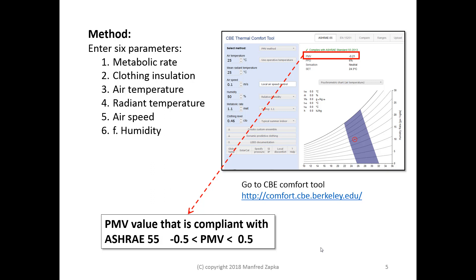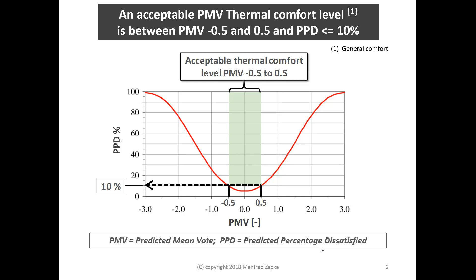The PMV is then used to calculate the PPD — Predicted Percentage of Dissatisfied occupants — meaning what percentage of occupants are dissatisfied with the thermal condition. We cannot have more than 10% dissatisfied. The PMV value must be between minus 0.5 and plus 0.5 in order to have a PPD value of 10% or less, and if we achieve this, we are compliant with ASHRAE 55.